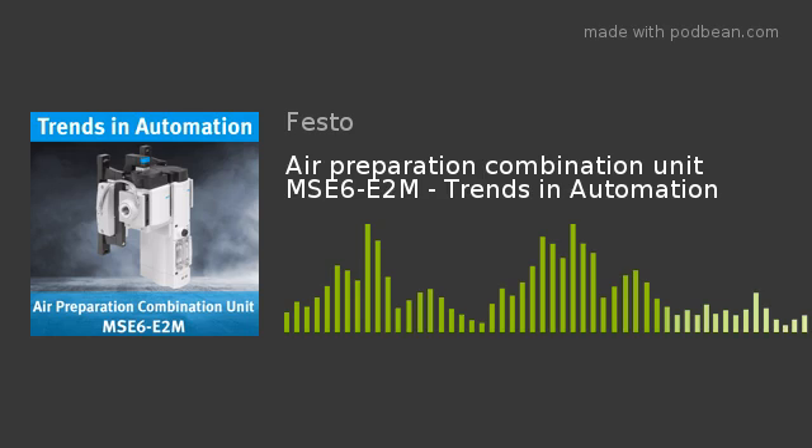Leakage can also be detected while the equipment is in operation. The E2M has the capability of detecting when there is a pressure drop greater than a predefined value, as well as a spike in flow above a predefined value. In both cases, this would indicate possible leakage and trigger a user-defined alert. Eliminating leaks not only saves energy, it also brings the equipment back to normal operating specifications, which ensures quality operation of the machine, optimum throughput, and higher overall equipment effectiveness — otherwise known as OEE.